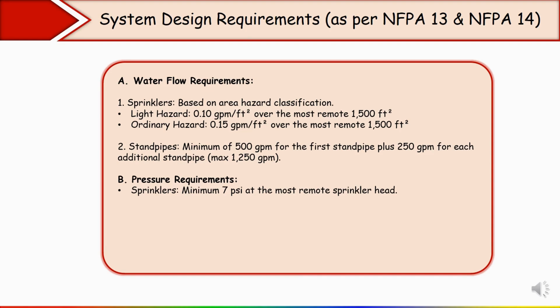Most remote sprinkler head means the sprinkler which is farthest from the water supply source or from the pump. That sprinkler is called the most remote sprinkler head. Suppose your pump is at the ground floor level and you have a 6th floor building, then the sprinkler on the 6th floor, the farthest sprinkler, is called the most remote sprinkler head.